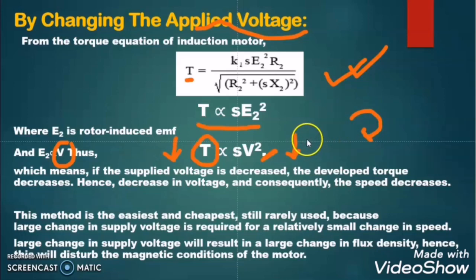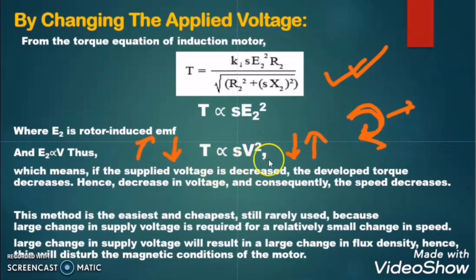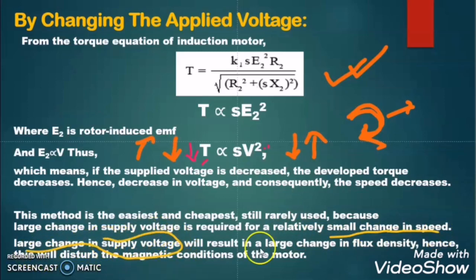In the opposite case, if we are increasing the voltage then the torque will increase, meaning we are increasing the rotating force of the rotor, thus increasing the speed of the motor. However, since torque is directly proportional to voltage squared, for a small change in the speed of the motor we need a large change in the supplied voltage. So the range of regulating the speed of the motor is very narrow when changing speed by varying the supplied voltage.